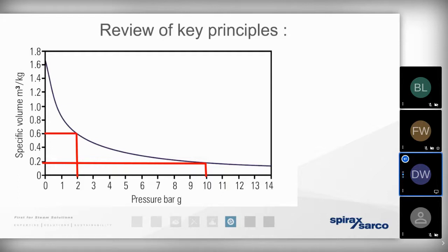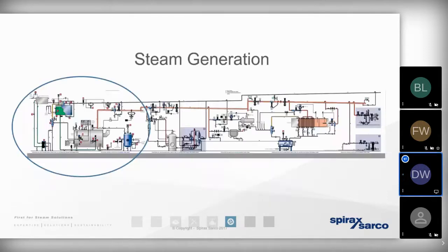Let's move forward and look at ways that we may be able to generate steam more efficiently in the future years. So it all starts in the boiler house or the energy center, the point of steam generation. And way back in March, when we undertook the first presentation in the series, Steam Fundamentals, we looked in some considerable detail with regards to how steam is generated in a traditional horizontal fire tube boiler. And we know that we're either going to use typically heavy oil, or we may even use gas to generate the steam. It's typically reliant upon fossil fuels.